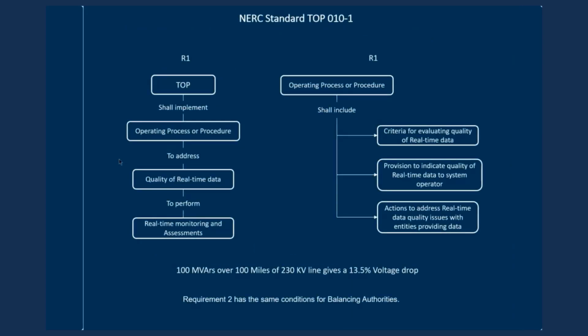The NERC standards that are most appropriate to this whole module is TOP 010-1. The requirement of that standard is that the transmission operator shall have a process or procedure to address the quality of the real-time data, to perform real-time monitoring and assessments.